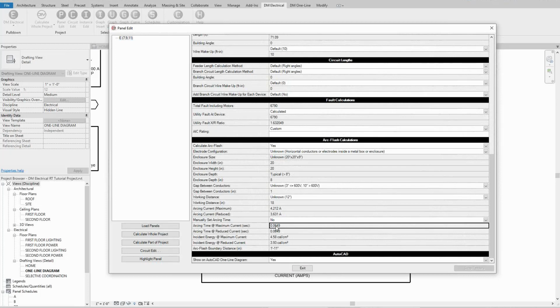And so if you've assigned a curve, we will give you the arcing time. If you haven't assigned a curve, we use a default value of 2, which is kind of the maximum that you ever assume that someone's going to stand in the arcing current. The assumption is they jump out of the way or are blasted out of the way after 2 seconds. And then based upon that arcing time, you can get the incident energy and the arc flash boundary values.